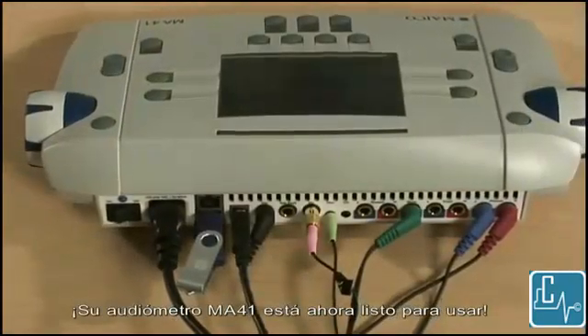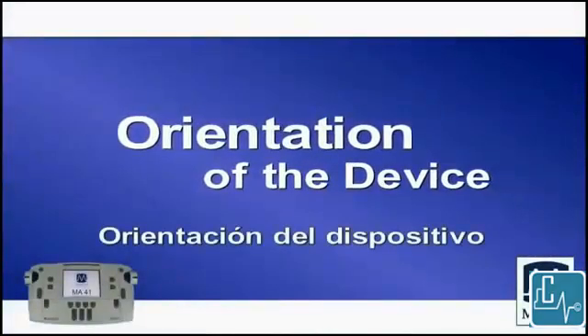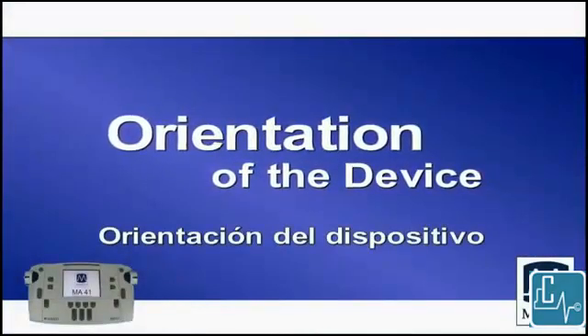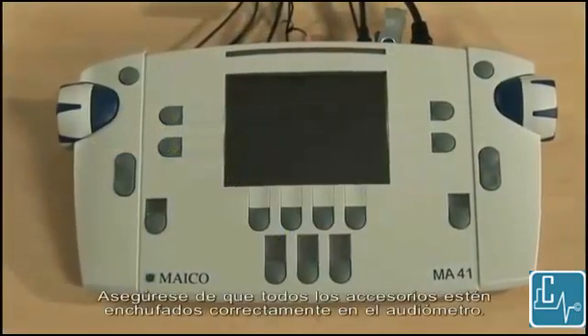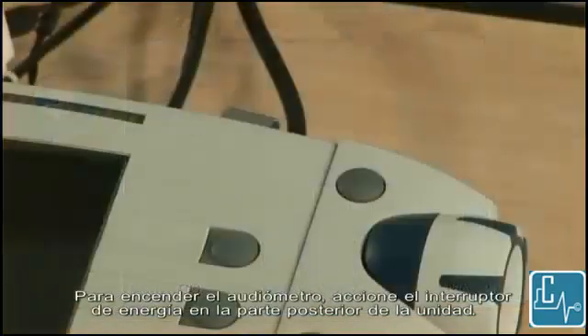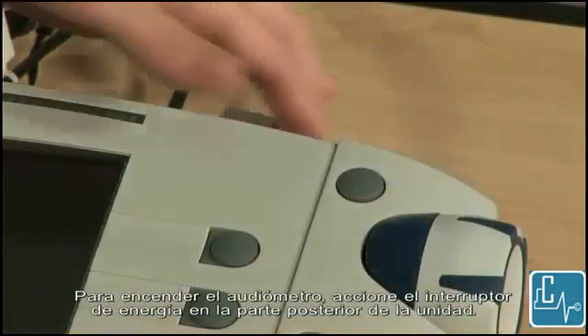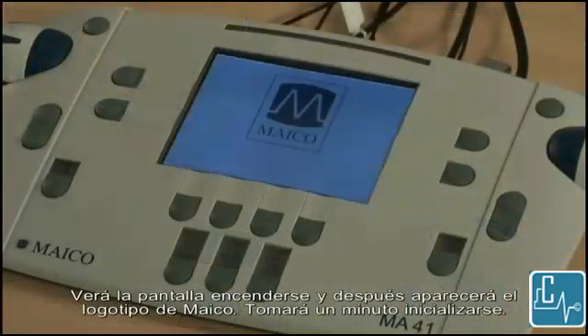Your MA41 audiometer is now ready to use. Make sure all of the accessories are properly plugged into the audiometer. To turn on the audiometer, flip the power switch on the back of the unit. You will see the screen display light up and then the Maico logo appear. It will take a minute to boot up.